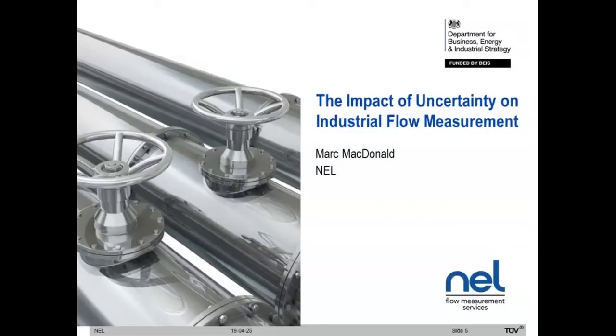In that time I've done lots of testing, research and calibration in NEL's flow facilities with various different types of flow meter, including single phase and multi-phase meters, as well as other different types of equipment. I've also worked on the design and upgrade of NEL test facilities and done consultancy work as well, including in uncertainty analysis. So measurement uncertainty is an area that's very important to NEL.